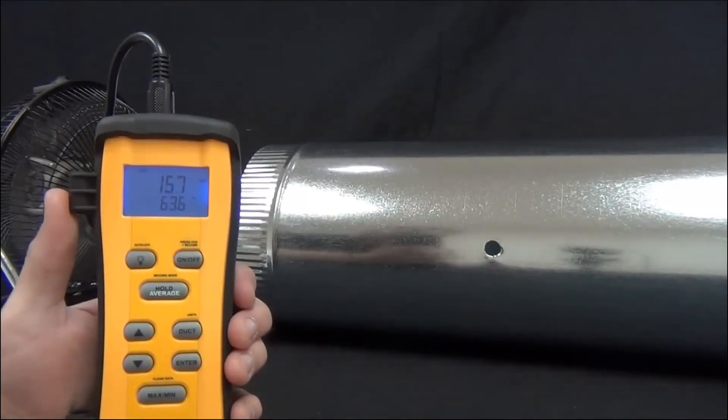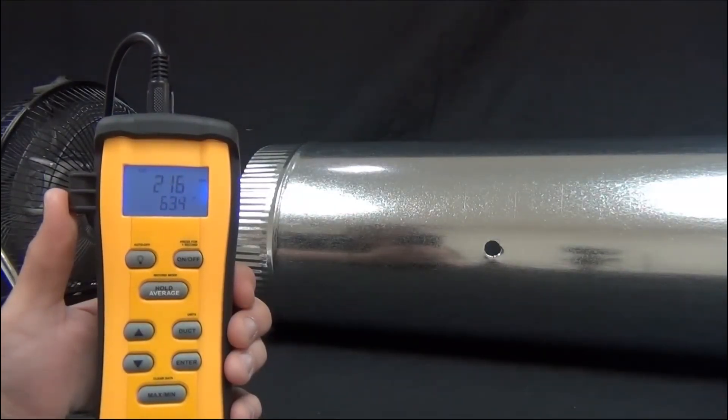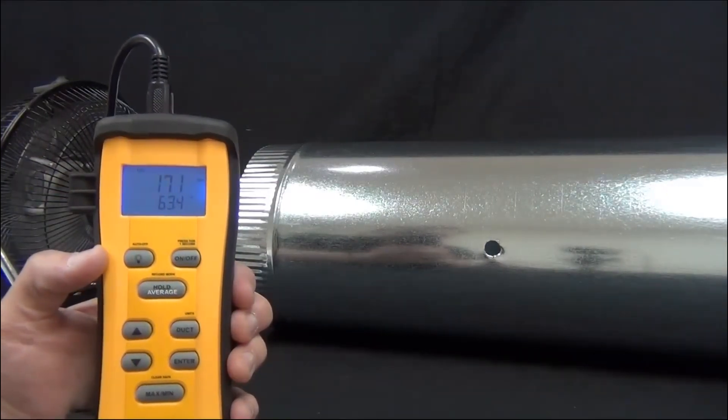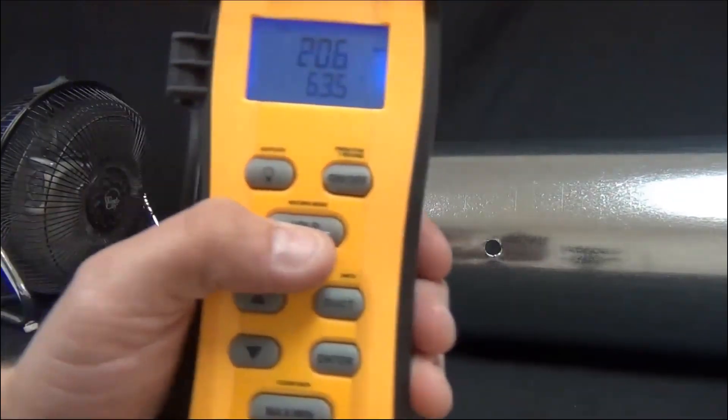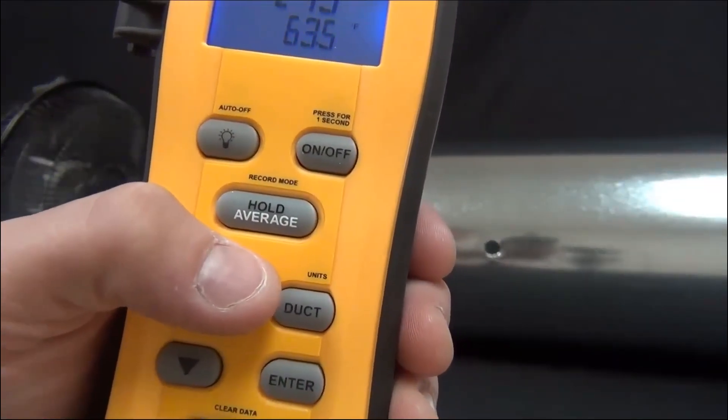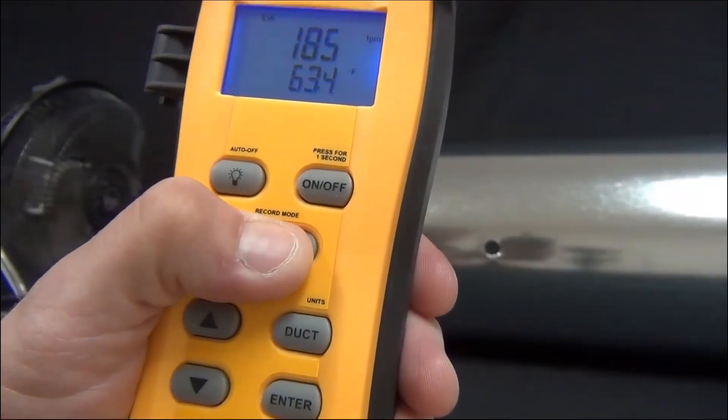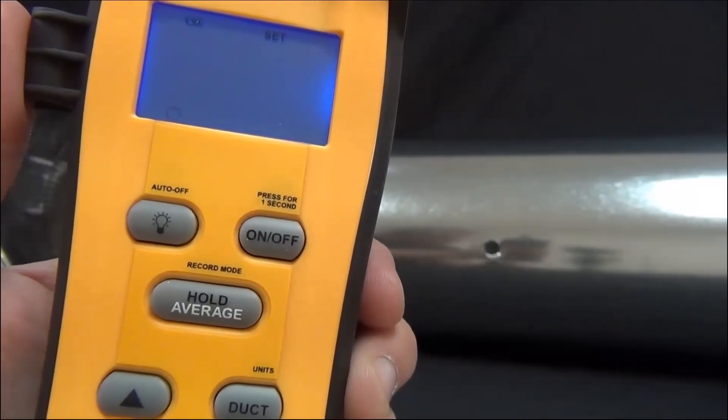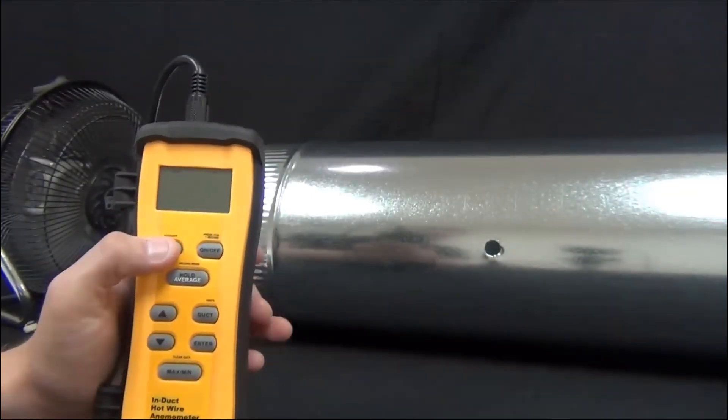The main function of the STA-2 is to get an accurate average CFM across the duct. The STA-2 does this in a couple different ways. The first way I'm going to show you is a timed average. So to get into record mode, you press the button above where it says record mode, it's the hold average button. So I'm just going to press and hold that down. And then you'll see that little stopwatch blinking that is the signal for a timed average. So I'm going to press enter to select that.